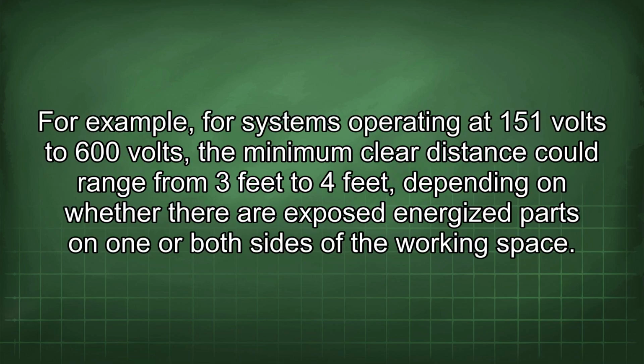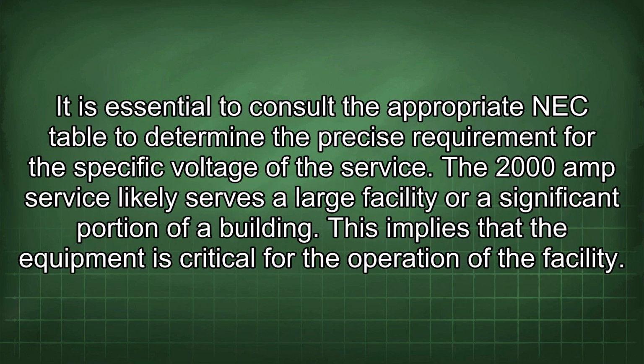For example, for systems operating at 151 volts to 600 volts, the minimum clear distance could range from 3 feet to 4 feet, depending on whether there are exposed energized parts on one or both sides of the working space. It is essential to consult the appropriate NEC table to determine the precise requirement for the specific voltage of the service. The 2000 amp service likely serves a large facility or a significant portion of a building.